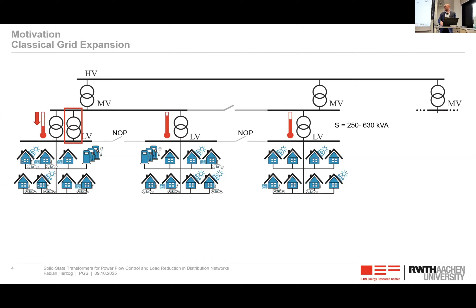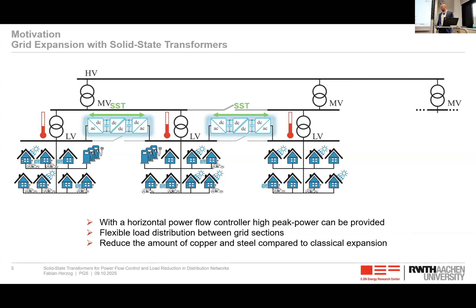So one option is to use solid state transformers, so basically AC to AC power electronic components. With this, we can have horizontal power flow between the grids because, for example, the most right grid section doesn't have charging infrastructure installed. It only has some private charging points. So this probably means a higher loading for the transformer because of the PV, because it has to feed back to the medium voltage grid section. So we can use the solid state transformers to transfer power from this grid section to the other grid sections which have a higher penetration of electric vehicles, for example. Using this approach, we can use the existing infrastructure, the cabling and the normal open coupling points to then couple the grid sections and have horizontal power flow, which is not possible in a classical AC distribution grid.